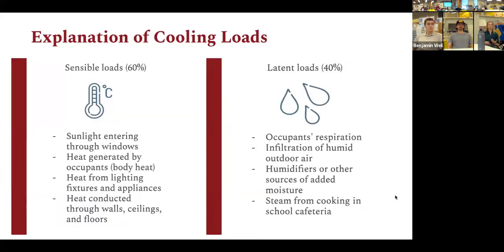When it comes to cooling, a quick explanation of what cooling loads are. Cooling can be divided into sensible loads and latent loads. Sensible loads, which account for about 60% of the load, are encountered through physical experience, such as sunlight, heat generated from occupants, heat from lighting fixtures and appliances, and heat conducted through the building envelope, like the walls, ceilings, and floors. The secondary load is the latent loads, which is about 40%, and it has to do with humidity, and it accounts for occupant respiration, infiltration of humid outdoor air, humidifiers, and other sources of moisture like steam from cooking.